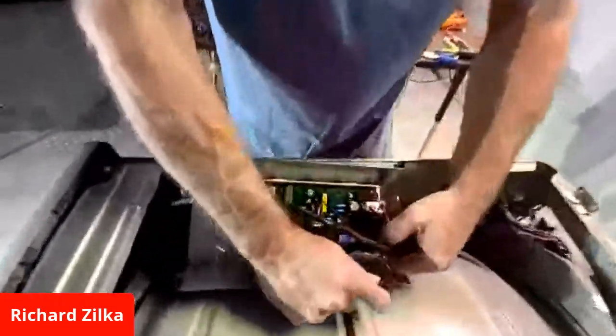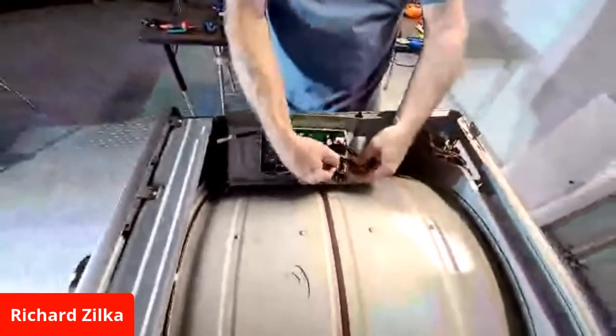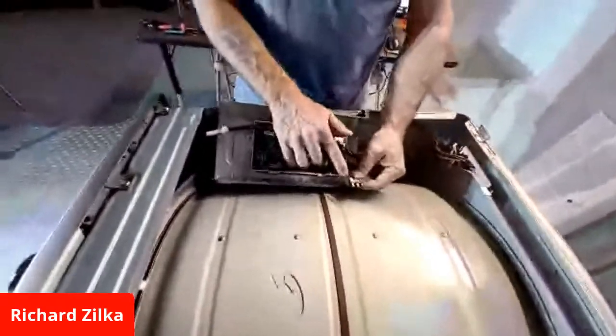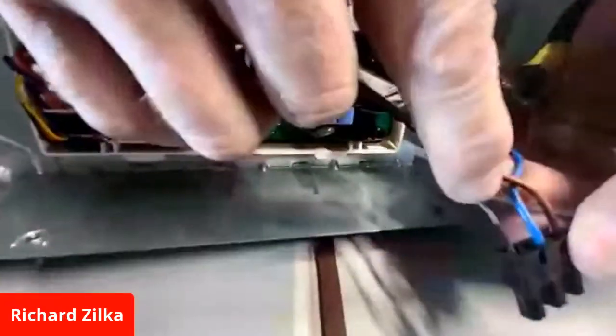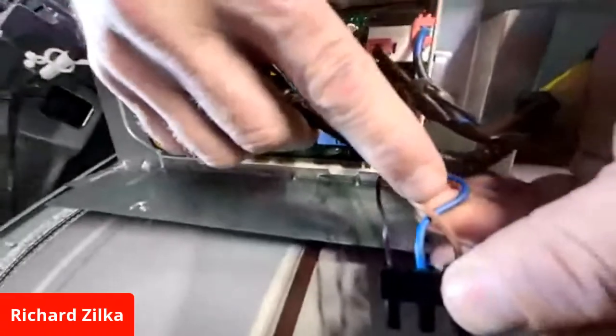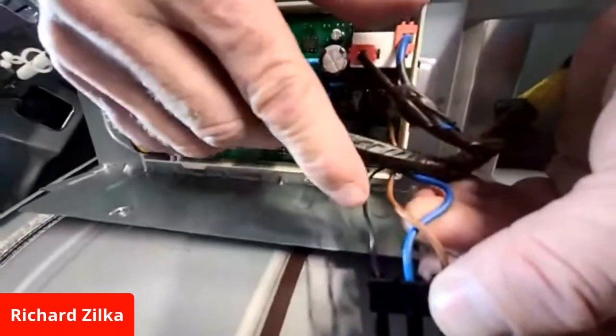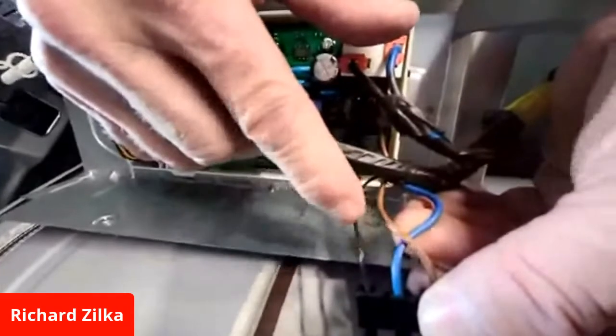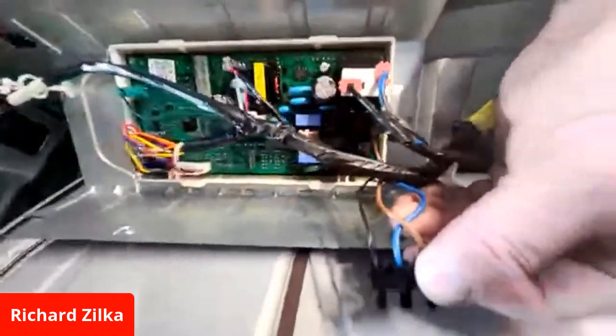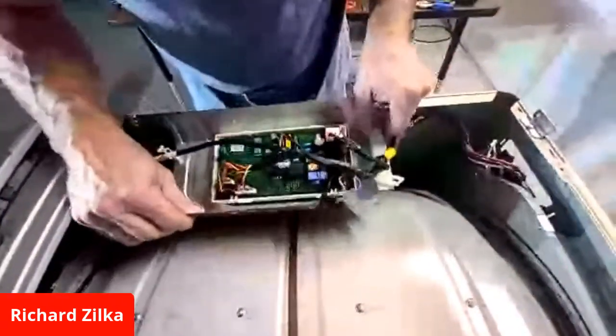Black is the power here. This really isn't a big power supply, but we don't need a lot. Notice the wire sizes—this black one is a lot smaller than the brown and the blue. The reason this gauge is smaller is it's only feeding the transformer on that board.